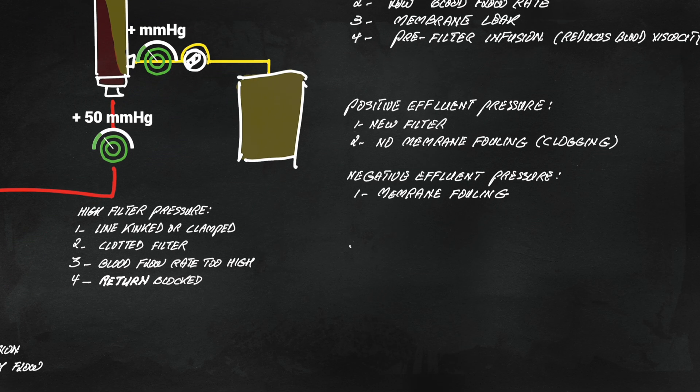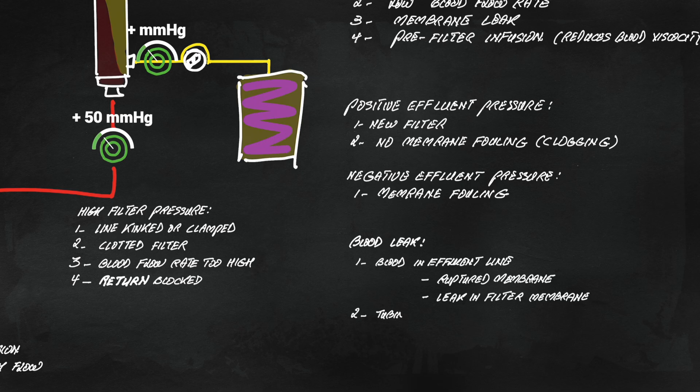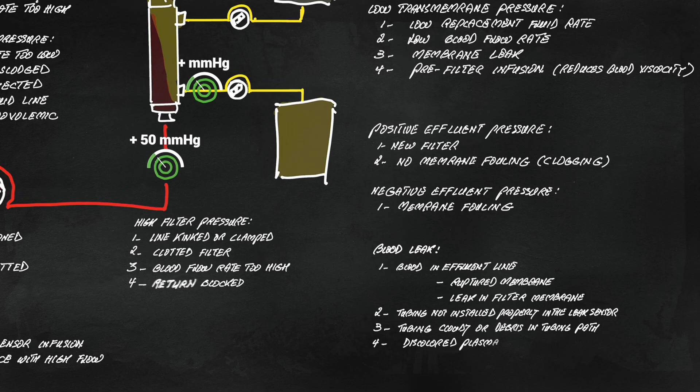Most machines will also have blood leak sensors, which sometimes can be triggered due to effluent fluid discoloration, for example due to high bilirubin levels.